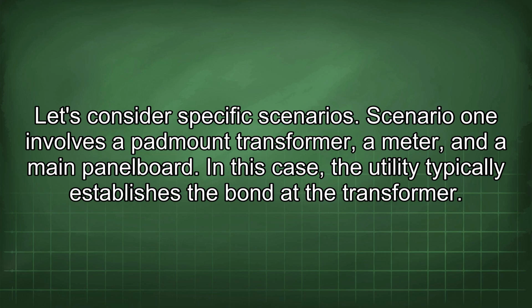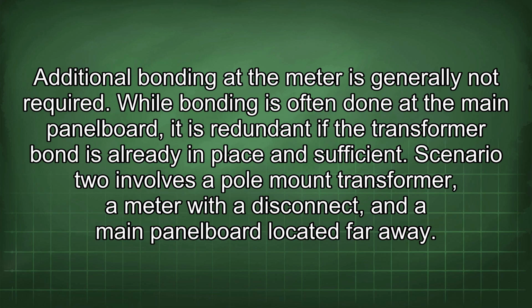Scenario 1 involves a padmount transformer, a meter, and a main panel board. In this case, the utility typically establishes the bond at the transformer. Additional bonding at the meter is generally not required.